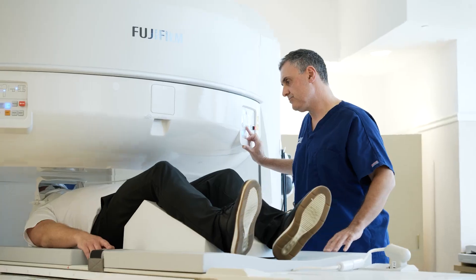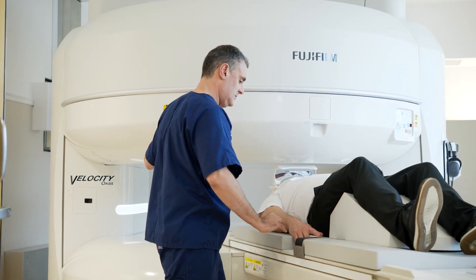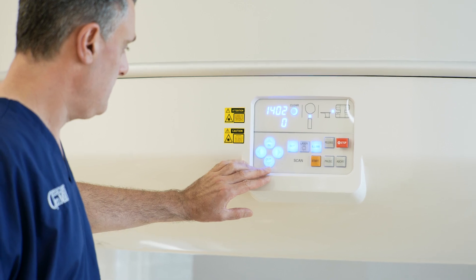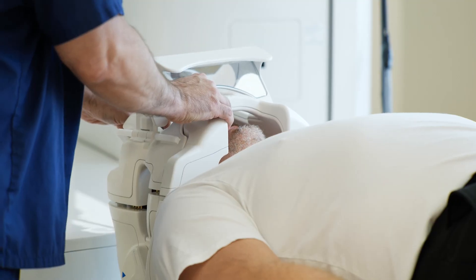With the new Velocity upgrade, the scan times are great, the blanket coil is great — it's more comfortable for patients, really light, and it fits the patient perfectly. The image quality has been outstanding, so it's a win-win. We don't have to switch from head coil to C-spine coil to do the bulk of our brain neurology work, and the table moves in and out faster. Those two things have really sped up setup time, and of course the protocols are faster.